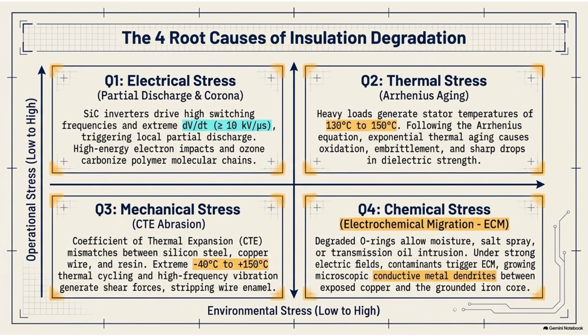But us? Severely. The sparks generate ozone, they create concentrated points of extreme heat, and they essentially bombard the polymer with high-energy electrons. The industry refers to this as corona aging. It basically carbonizes the plastic, taking these microscopic bites out of the insulation over time until it finally cracks. Okay, so you have thousands of microscopic sparks slowly eating the insulation.